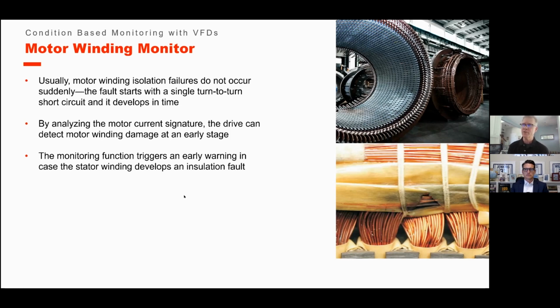The monitoring function triggers the early warning for the stator if you have that insulation fault. A good point to mention here is there are 2 values that do not need external sensors. One of them is the motor winding. The drives today are extremely sophisticated. They have a ton of sensors in them. They have extremely high-powered processors. I've been in this many years. I've been in this since the 80s when drives came out, and they basically blew up.